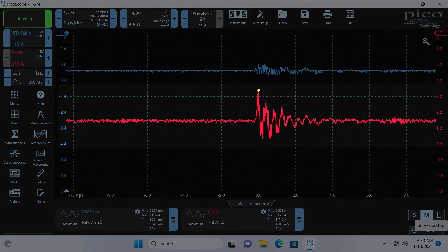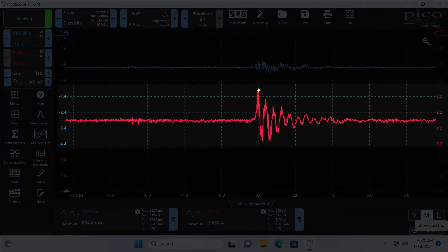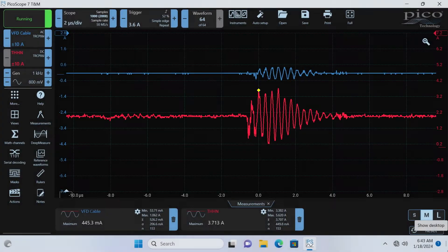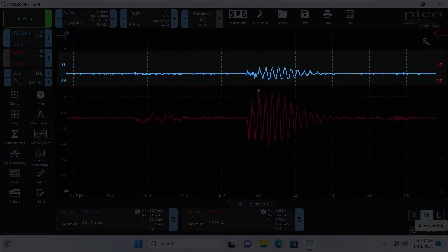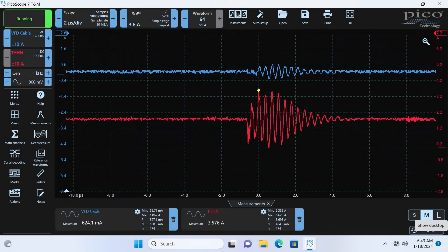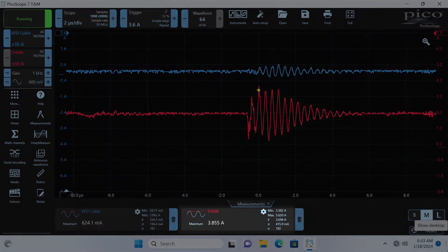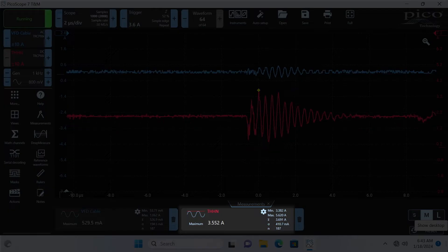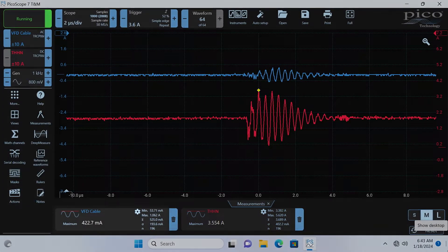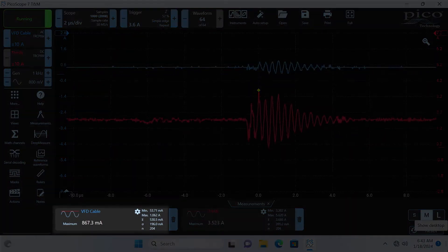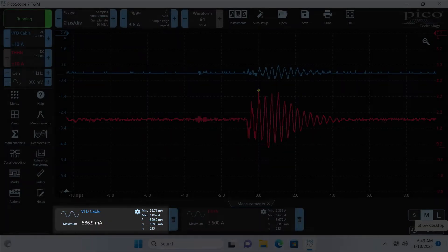As we look at the data, we can see that the red trace, which is the THHN motor shaft current, versus the blue trace, the VFD cabled motor shaft current. You can see that the THHN, we're looking at up to about 4 amps of current spikes on that motor shaft compared with consistently less than a single amp on the VFD cable.